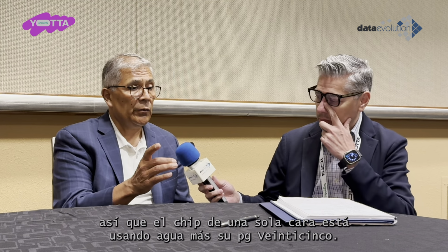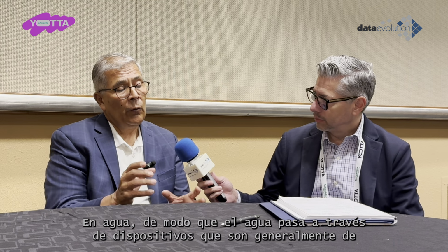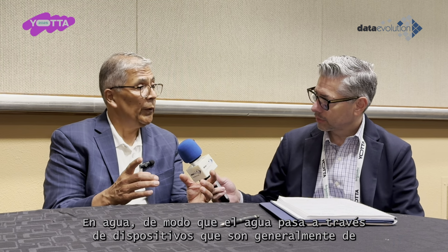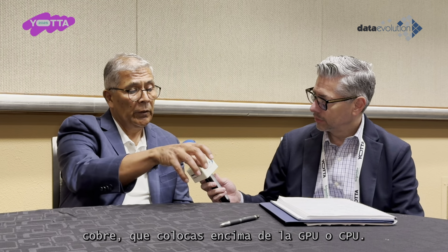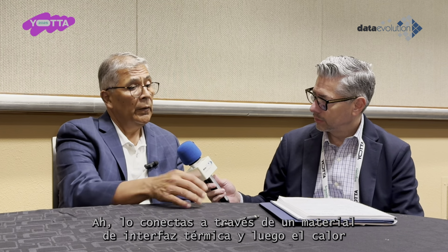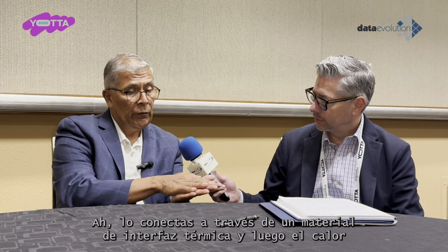So single phase direct to chip uses water plus ethylene glycol, called propylene glycol, PG25, 25% propylene glycol in water, basically antifreeze in water. That water passes through devices called coldplates, usually made of copper, placed on top of the GPU or CPU. You attach it through a thermal interface material, and then the heat from the GPU or CPU gets transmitted through the thermal interface material into the coldplate, and then transported out by the water.